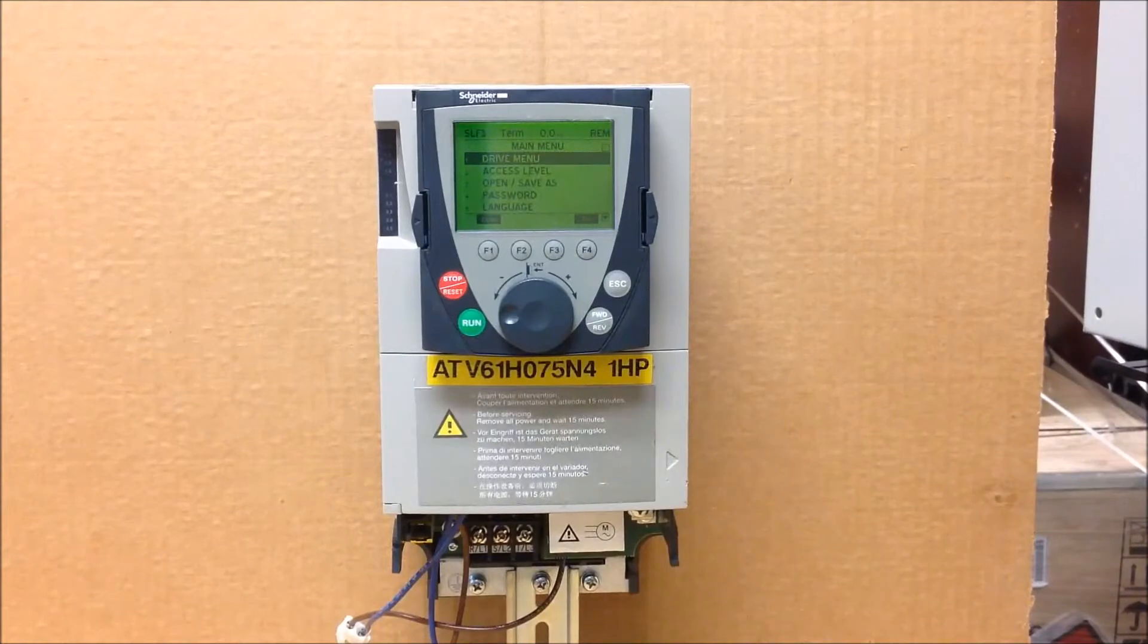You have to keep in mind that you actually can go ahead and download some of the menus. You have the option of choosing all the menus or you can choose individual menus or even parameters to download. So there is some room for movement there, but if you have a different firmware version when you go from one drive to the next, this particular function will not be available for you to do.